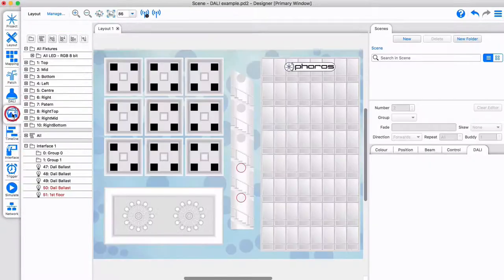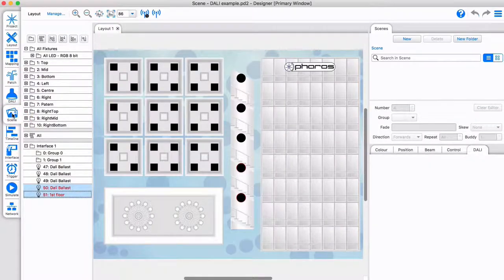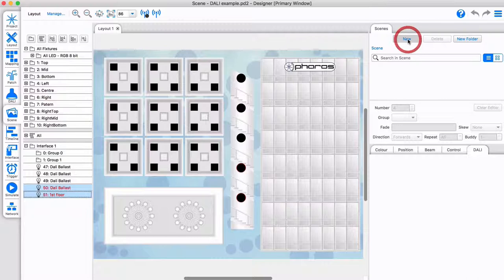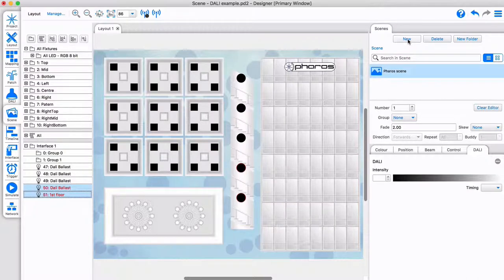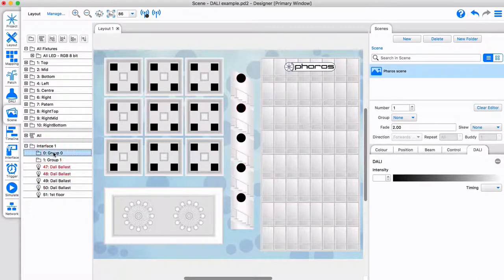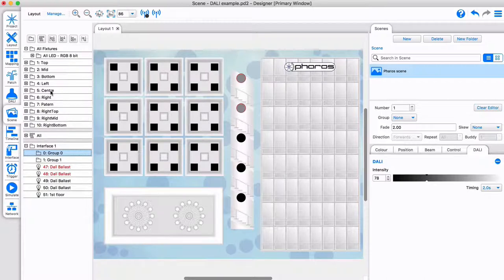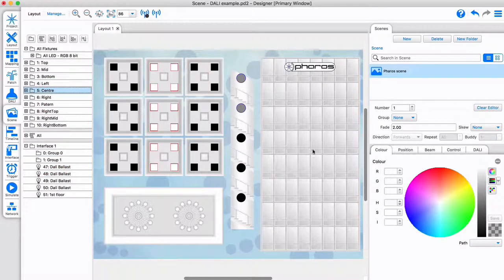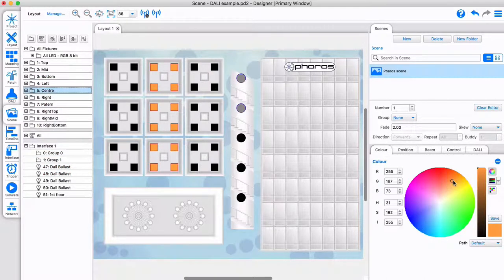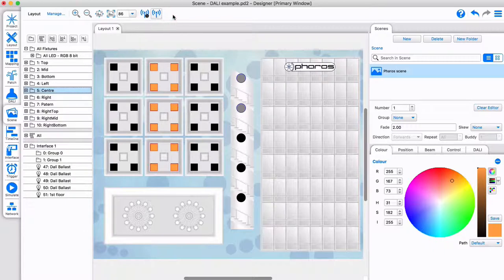We can include DALI and Pharos designer scenes together with other fixtures. Upon recall, Pharos does not use the DALI scene command but sends the required value to each fixture. This gives you 256 scenes to use and can be outputted live.